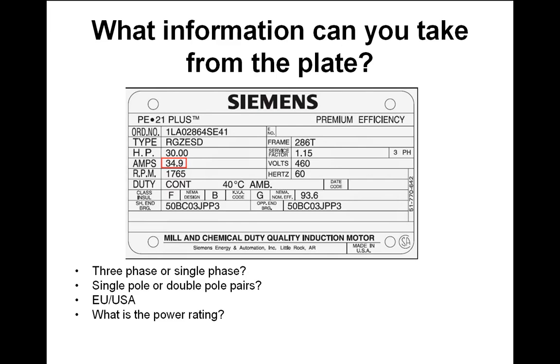Nick worked out the double pole pairs from the RPM figure — spot on. If it's running at 60 Hz, synchronous speed should be 3600 RPM. The motor shows 1765 RPM, which is close to half of 3600 — so it must be two pole pairs. The power comes out to approximately 16 kilowatts.